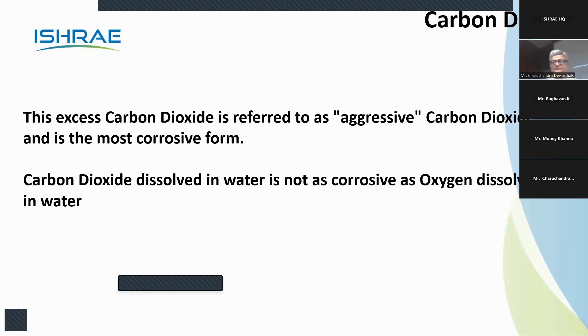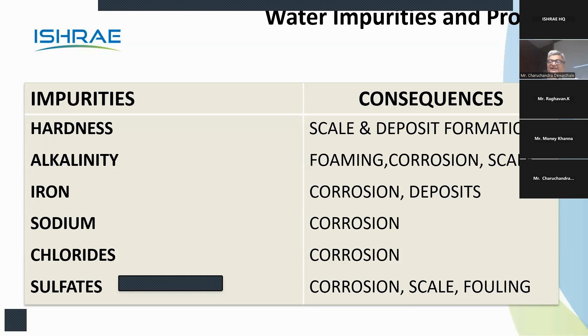So I will sum it up. Hardness, scale deposit formation, alkalinity, foaming, corrosion, scaling. These are the issues. Iron, corrosion and deposits, sodium corrosion, chlorides corrosion, sulfates corrosion, fouling, scaling again. Silica, in our case, I have not discussed at length because our water is not so aggressive. Aggressive water is boiler, where silica plays havoc. And in a power plant boiler, silica will play very, very high havoc. But in our case, temperatures are low, so silica doesn't play too much. So I have not touched it. Oxygen corrosion, CO2 corrosion, hydrogen sulfide corrosion, fouling, ammonia corrosion, oil and grease, very high amount of corrosion and fouling.